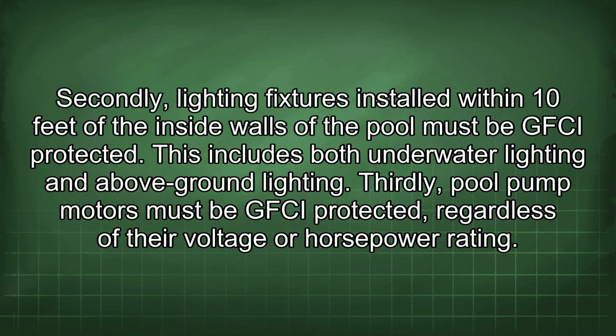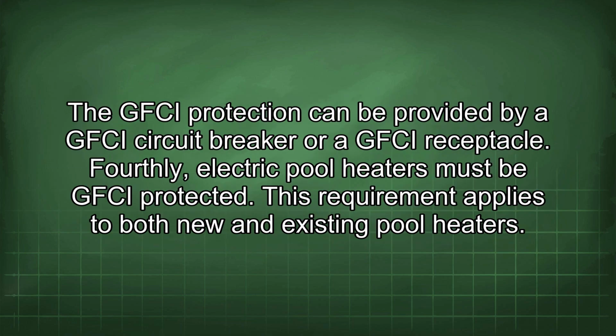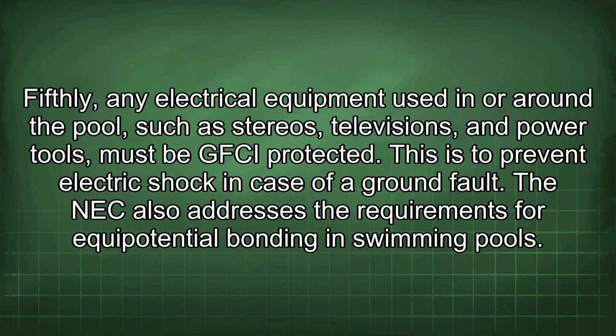Thirdly, pool pump motors must be GFCI protected, regardless of their voltage or horsepower rating. The GFCI protection can be provided by a GFCI circuit breaker or a GFCI receptacle. Fourthly, electric pool heaters must be GFCI protected. This requirement applies to both newer and existing pool heaters. Fifthly, any electrical equipment used in or around the pool, such as stereos, televisions, and power tools, must be GFCI protected. This is to prevent electric shock in case of a ground fault.